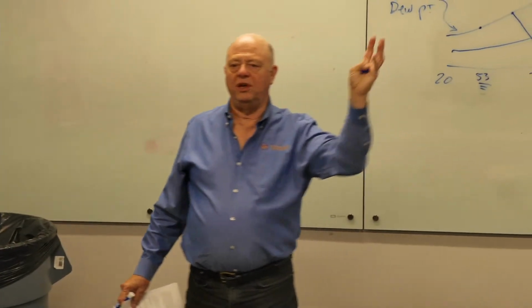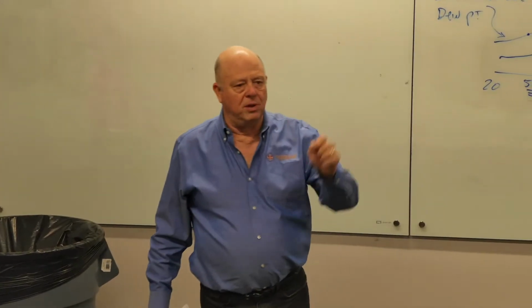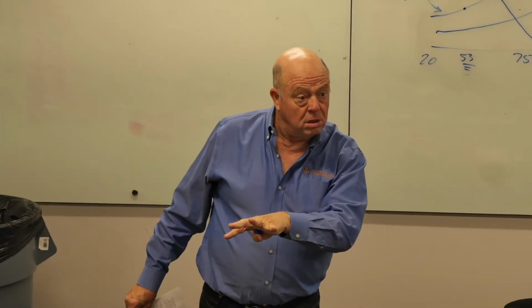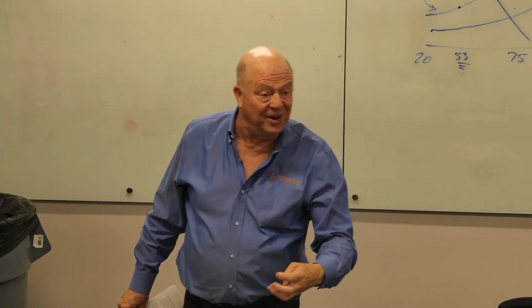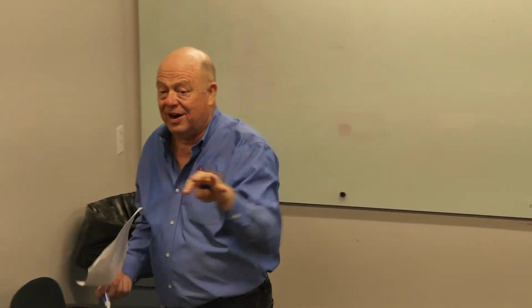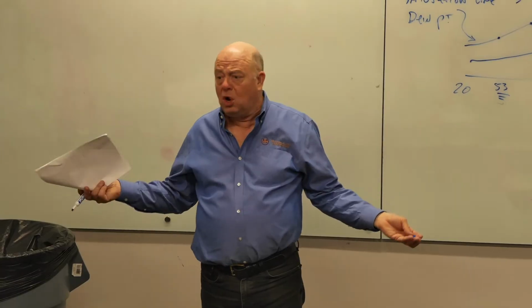Let me ask you a question. How often do we insulate condensate drain lines? Not often. Not often is the right answer. Now, if this is within a conditioned space, it's probably not a big deal. Probably the condensate, which is cold, right? It just came off of a cooling coil. And if everything's working right, it hits the drain pan and it goes to the drain line, and it's kind of warming as it goes. But as it goes down that drain line, it's still pretty cold. But in a conditioned space, you're probably fine.